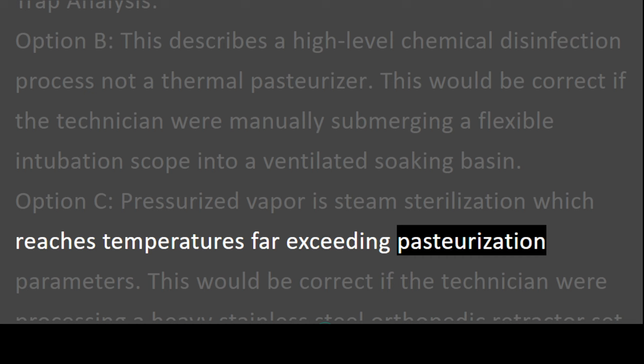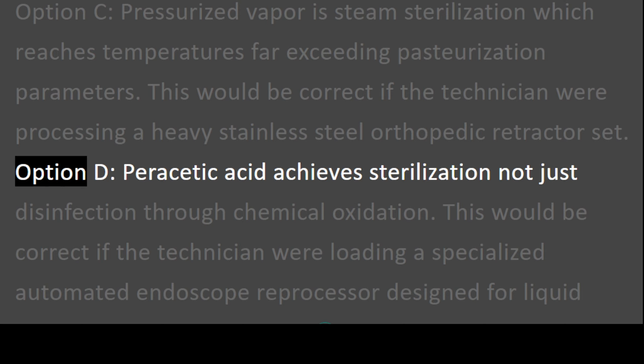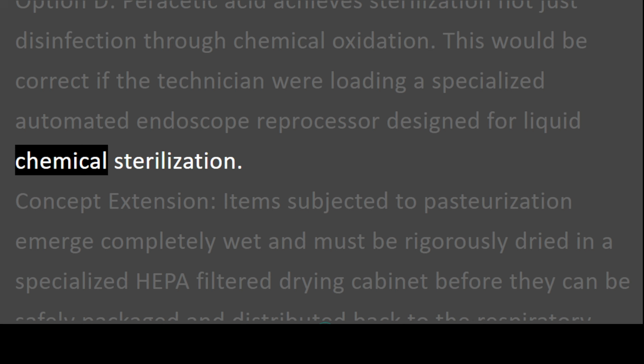Trap analysis. Option B. This describes a high-level chemical disinfection process, not a thermal pasteurizer. This would be correct if the technician were manually submerging a flexible intubation scope into a ventilated soaking basin. Option C. Pressurized vapor is steam sterilization, which reaches temperatures far exceeding pasteurization parameters. This would be correct if the technician were processing a heavy stainless steel orthopedic retractor set. Option D. Peracetic acid achieves sterilization, not just disinfection, through chemical oxidation. This would be correct if the technician were loading a specialized automated endoscope reprocessor designed for liquid chemical sterilization.